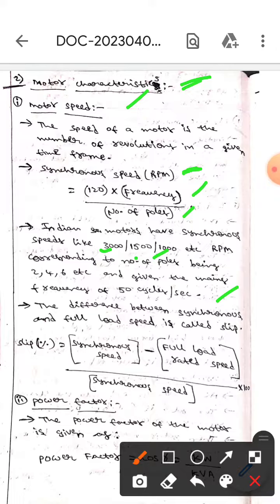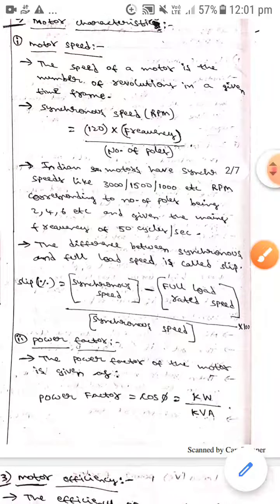The difference between the synchronous and full load speed is called slip. Slip percentage equals synchronous speed minus full load rated speed divided by synchronous speed times 100. The next characteristic is power factor.